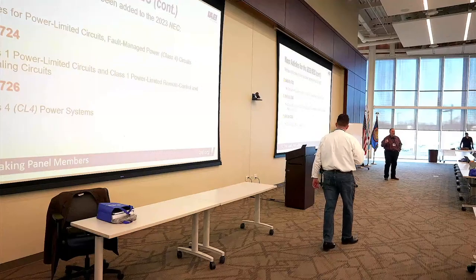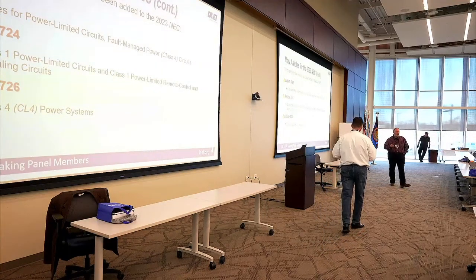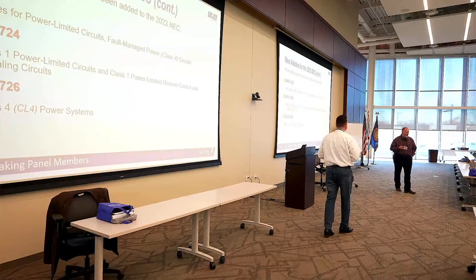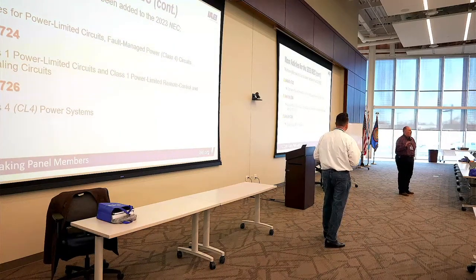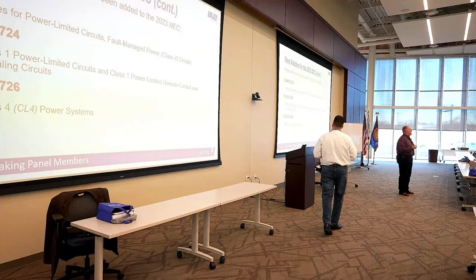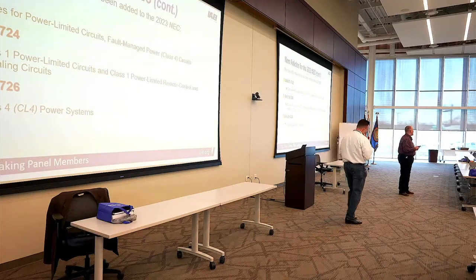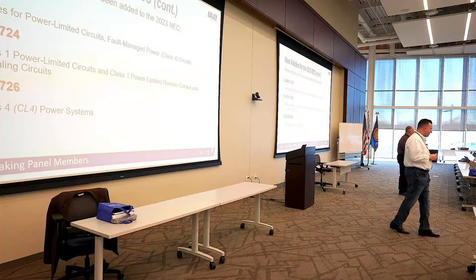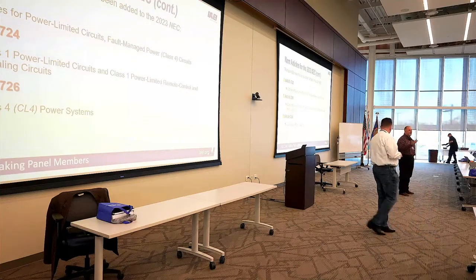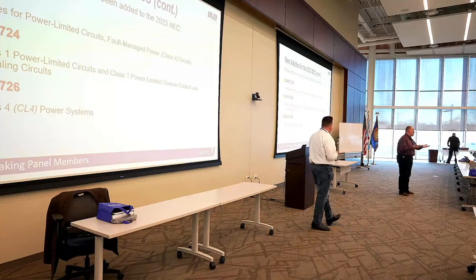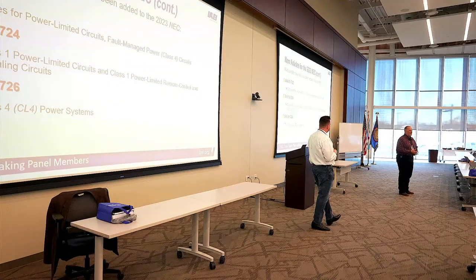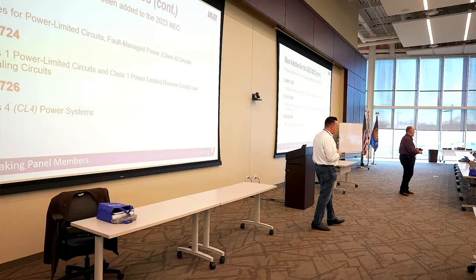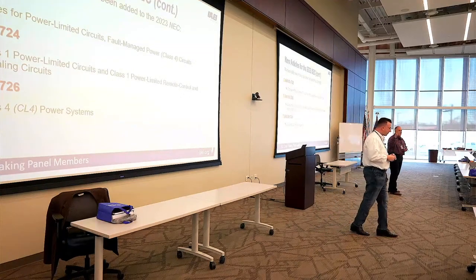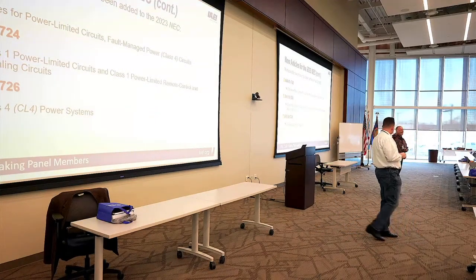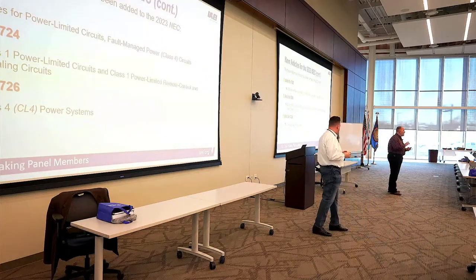Power limited, this was another big one. There's a company in California that created what they call pulsed power, and it was totally new. They listed it to standards that were basically for information technology, putting upwards of 400 volts across 10 base T type conductors. Think about chapter 8 wiring methods, right? Chapter 8 stands on its own. We don't really care about bundling, or the qualified person installing it, and all that. So they had this technology being wired and applied like a chapter 8 wiring method, but with significant power.